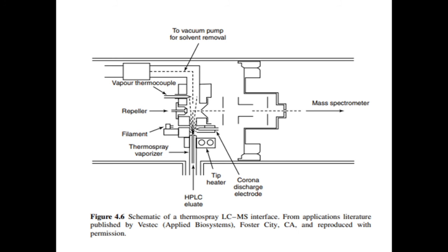It must also be remembered that repeller-induced fragmentation, like MSMS, does not produce an electron ionization spectrum, and while interpretation may be attempted using the same principles, library matching is not valid unless against repeller fragmented spectra.